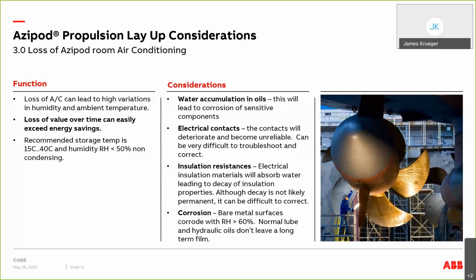Oftentimes, once an AC system is shut down, particularly in spaces in the vessel that are in contact with the water, condensation quickly ensues, and we start having all kinds of problems that sometimes are very hard to troubleshoot, particularly with items such as electrical contacts. Once the contact surfaces become corroded, then the contact is unreliable. It may be making intermittent connections, it may not be. And again, those are very hard to troubleshoot often. So again, the recommendation would be to keep the AZIPod room air conditioning running at all times.